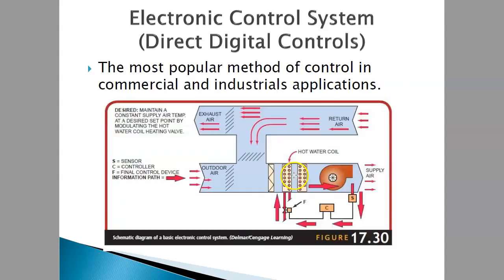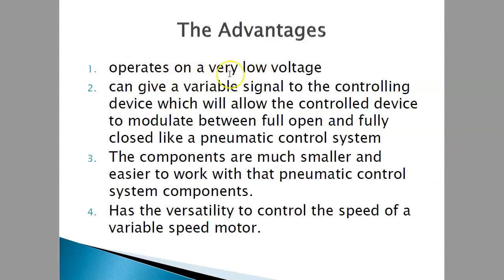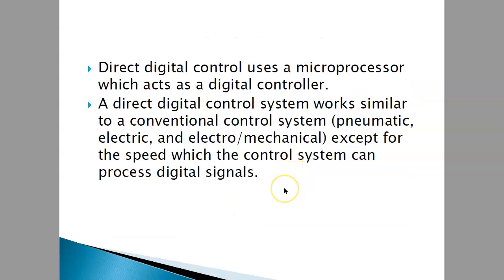Okay, what are the advantages of an electronic control system or direct digital control? It operates on a very low voltage. It can give a variable signal to the control device, which will allow the control device to modulate between fully open or fully closed, like a pneumatic control system. Then the components are much smaller and easier to work with, and could control a variable speed motor. This is an electronic control device. Direct digital control also uses a microprocessor acting as a digital controller.